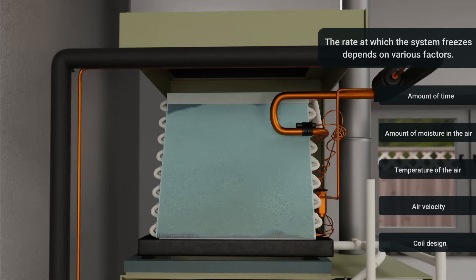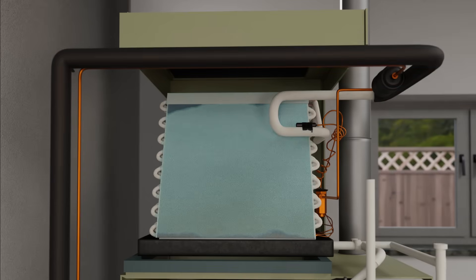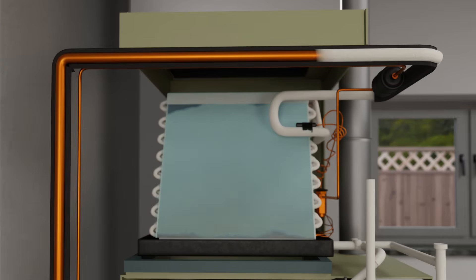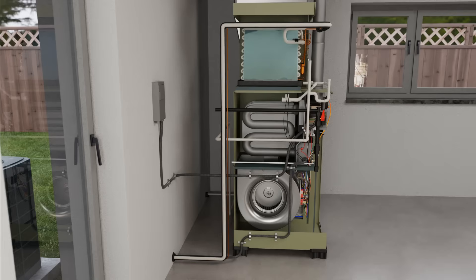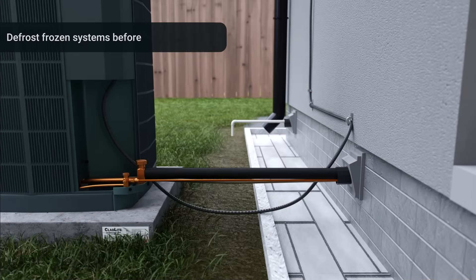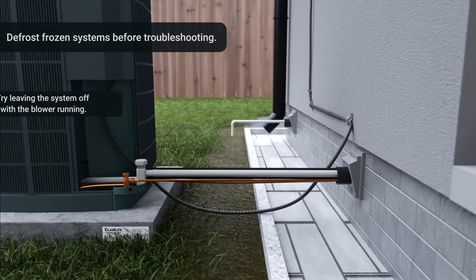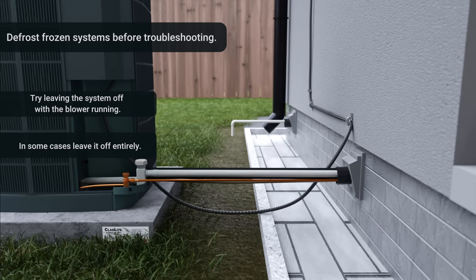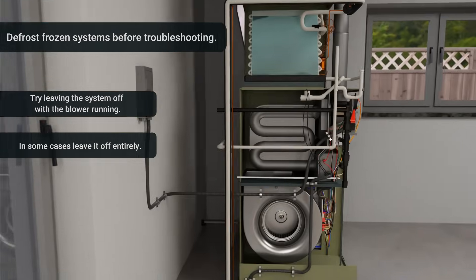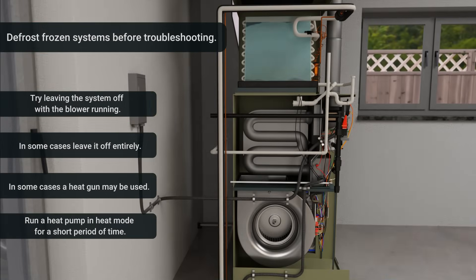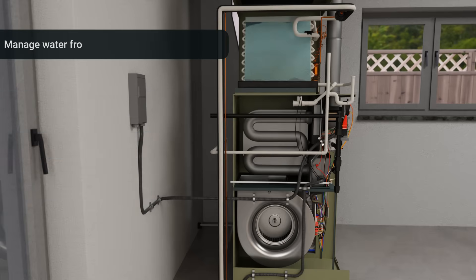The ice buildup almost always starts in the evaporator coil and works its way outside. If you find a frozen system, take your time to fully defrost it before doing any troubleshooting. Leaving the system off with the blower running is often a good strategy. In some cases you may need to leave it off entirely, and in some cases you may be able to use a heat gun or run a heat pump in heat mode for a short period of time. Always make sure to manage the water as the ice melts so as not to cause water damage.